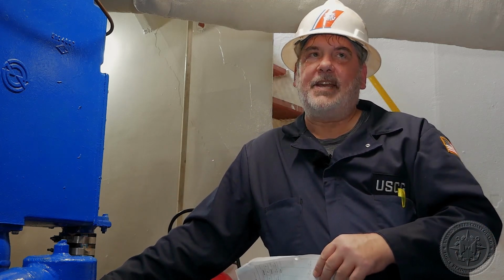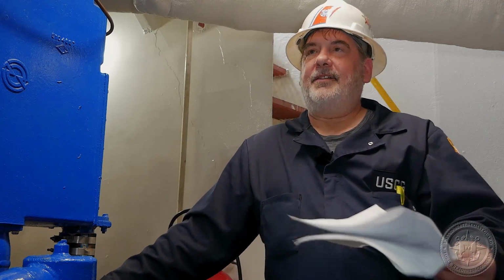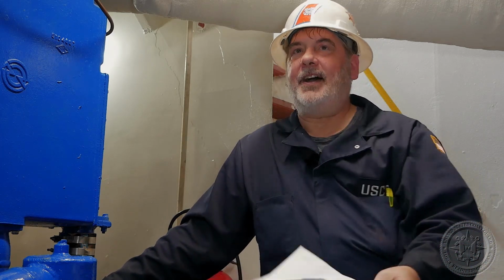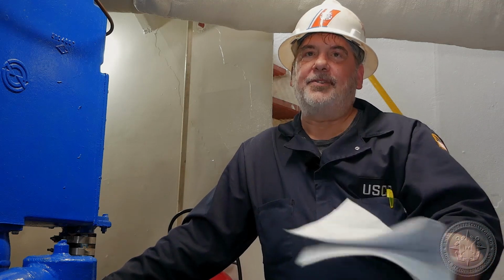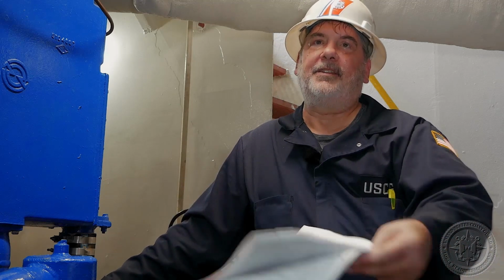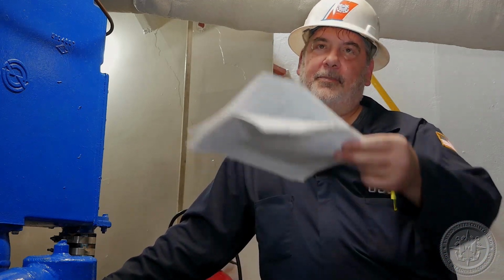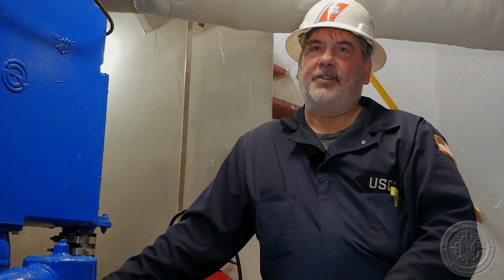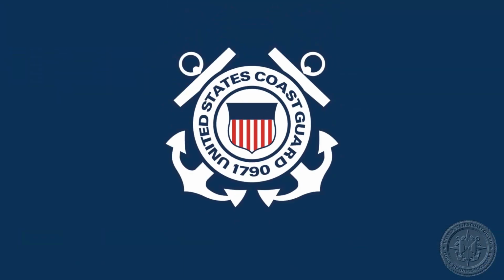least dangerous type of fuel leak is when it's just weeping out of either a corroded point on the pipe or at a connection point. So when you write your deficiencies on these, you may want to qualify the type of leak in those terms and let your verifying officer help you determine what level of control action and how long you're going to give them to correct this deficiency.